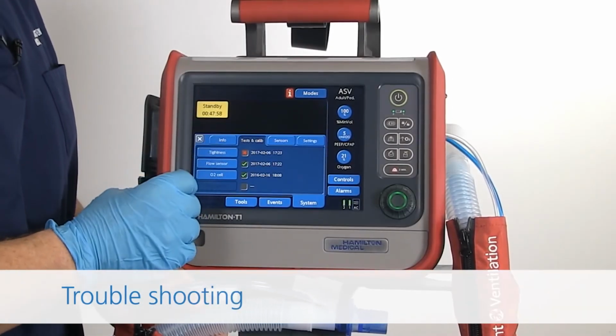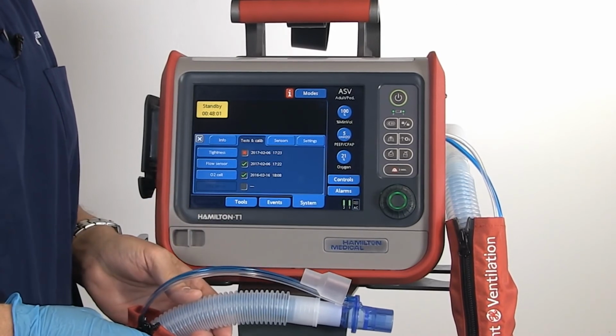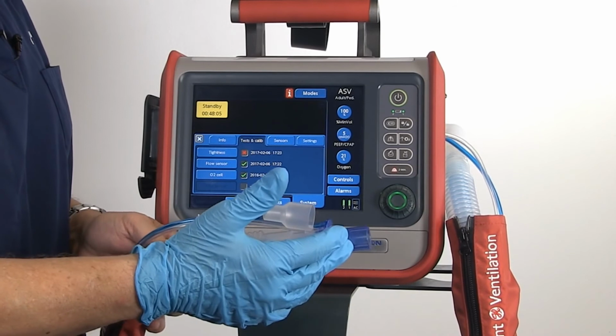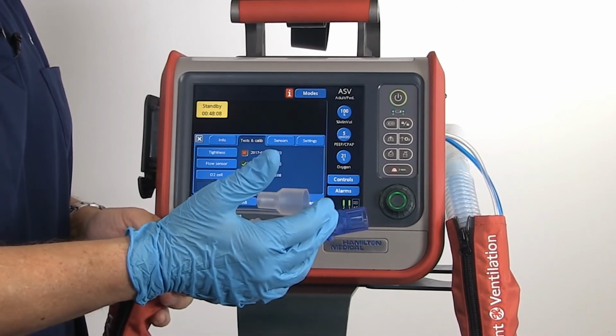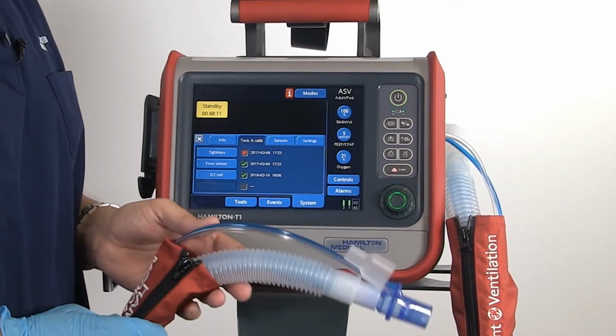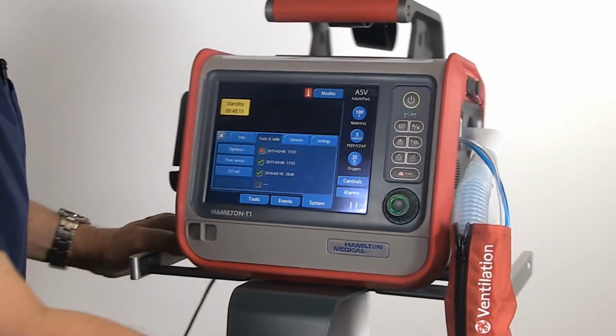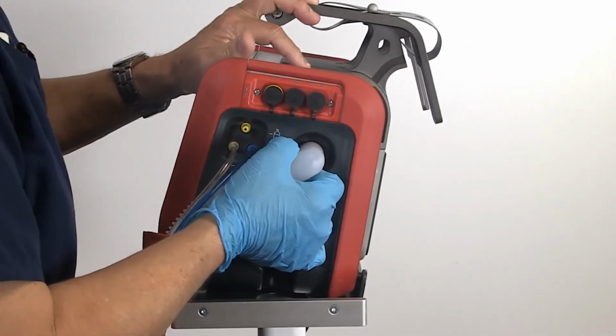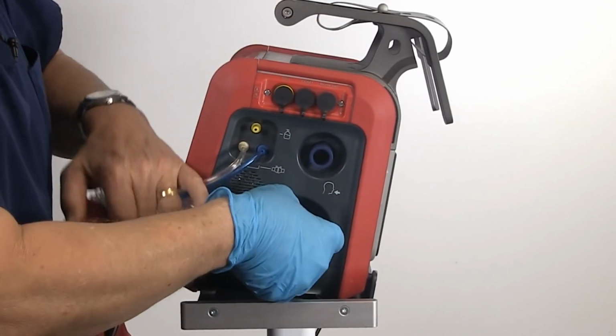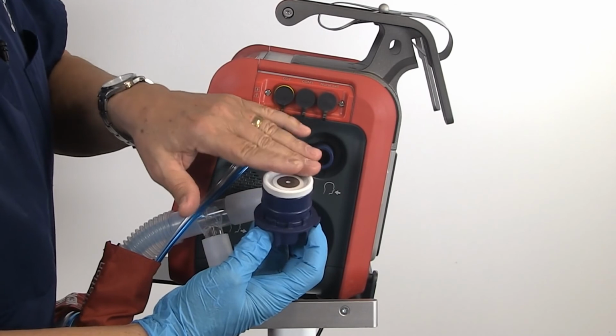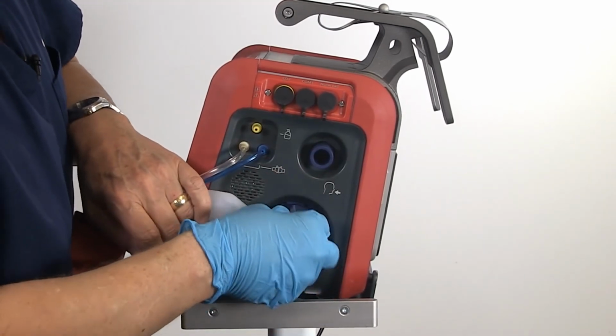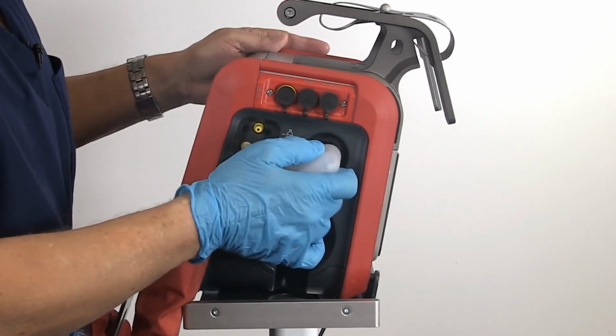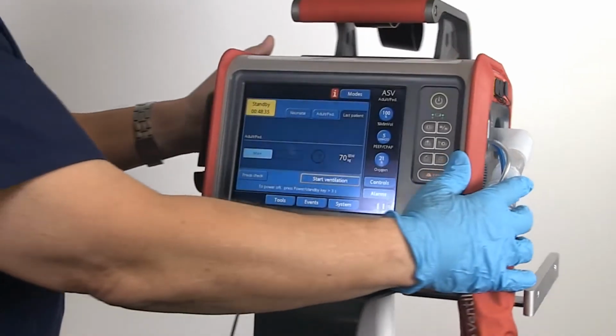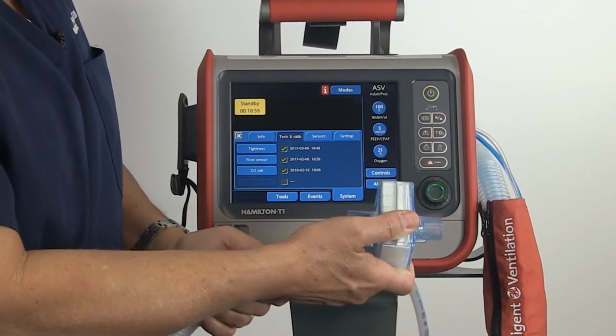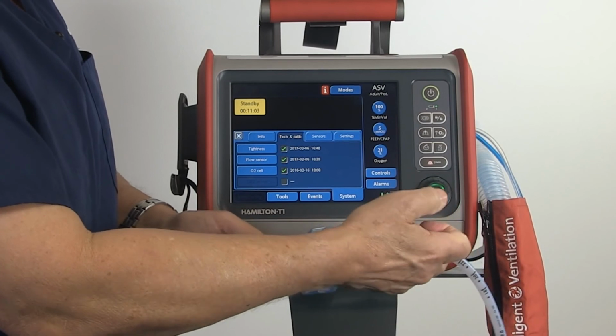If you receive a red X in either one of the boxes, that indicates a failed test. At this time, you should check your circuit from the flow sensor all the way back to the ventilator to assure all connections are tight. You should also remove your exhalation valve, check the membrane for proper positioning, reinsert it, and tighten it. Attach your circuit and rerun your pre-op checks. After passing your pre-op checks, you're now ready to set your controls, place your filter in line, and begin ventilation.